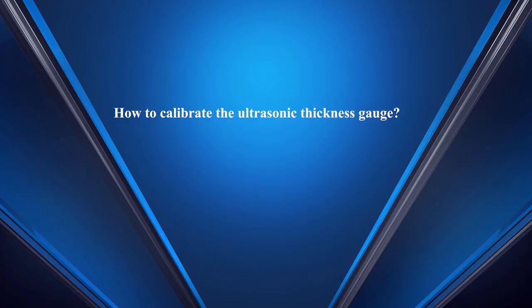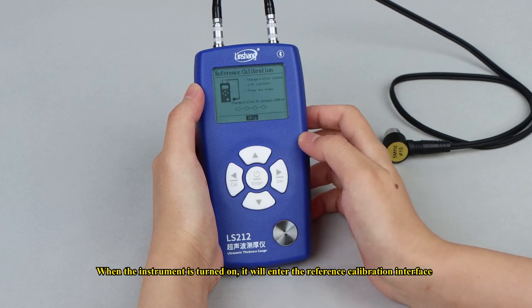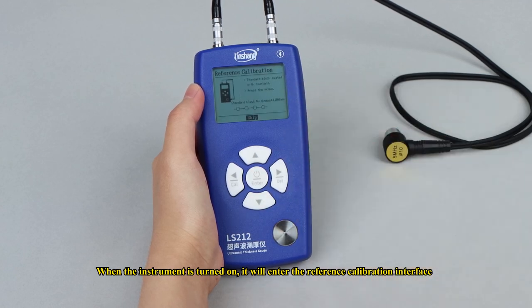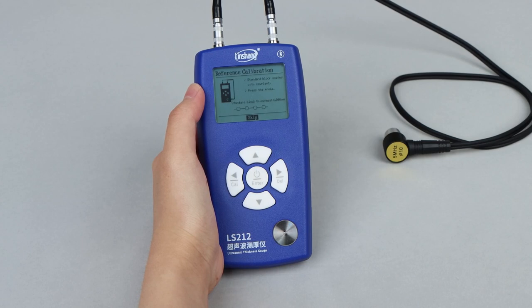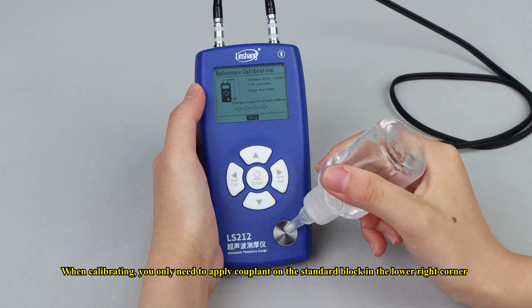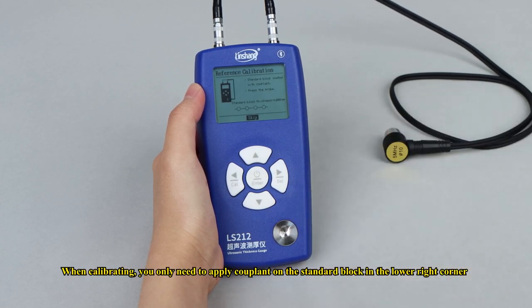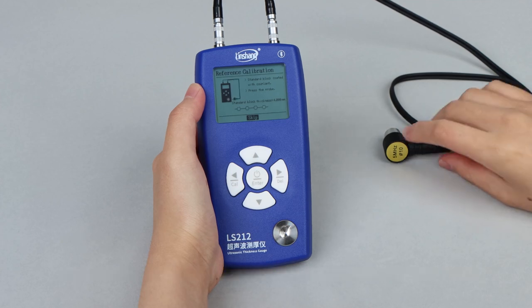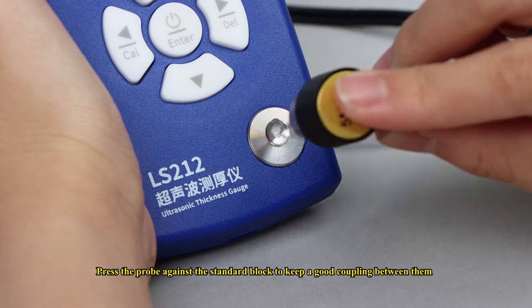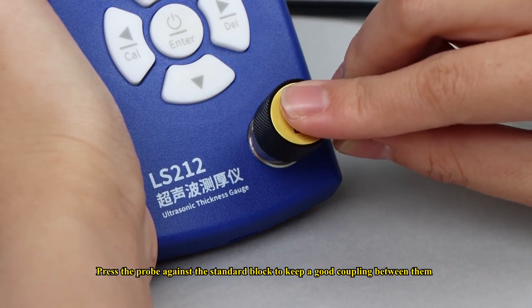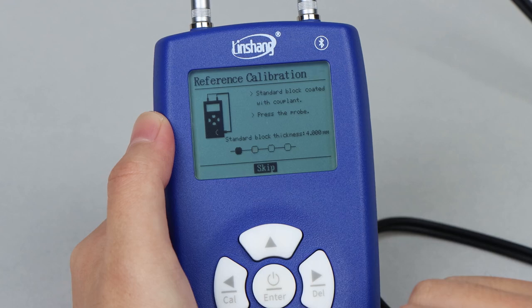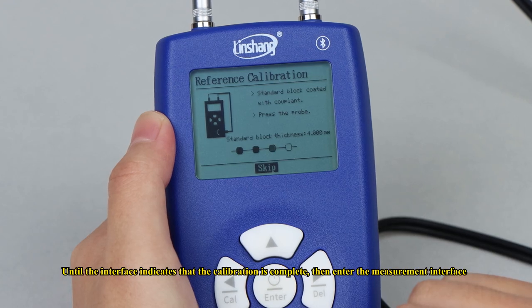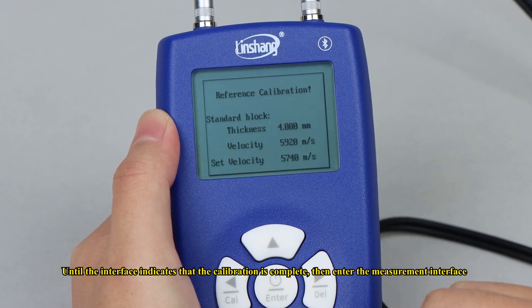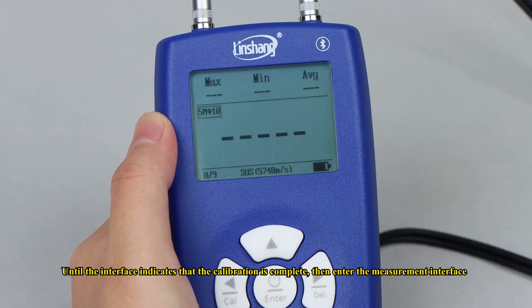How to calibrate the ultrasonic thickness gauge. When the instrument is turned on, it will enter the reference calibration interface. When calibrating, you only need to apply couplant on the standard block in the lower right corner. Press the probe against the standard block to keep a good coupling between them, until the interface indicates that the calibration is complete, then enter the measurement interface.